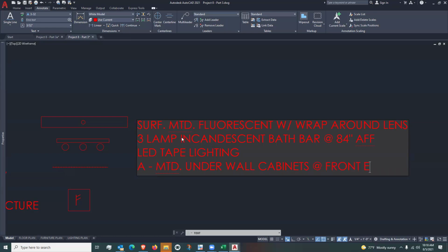Front edge. Paul, can I ask another question? It's Rebecca. I have a lot of them today. When it's above finished floor, can you reconfirm, is that to the base of the fixture or outlet, or to the center point of the fixture or outlet? It's actually to the center point of the junction box. Okay. So let's talk about a sconce fixture that hangs on the wall. When you are looking at that sconce fixture, that J box or junction box is usually somewhere in the middle of the fixture.